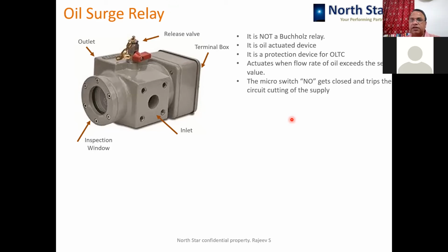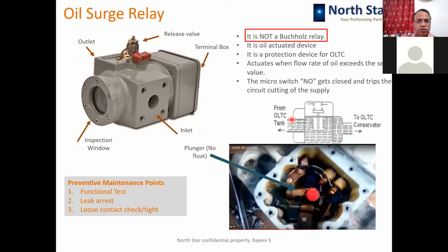So when the OSR operates, it is an indication that there is excessive arcing happening inside the OLTC. So you should look at the OLTC to see why that excessive arcing is happening. Maybe you have to take an immediate shutdown and do the necessary maintenance or replacement of the defective contacts, or you have to hold the OLTC operation and continue with the transformer working. So that is about the OSR. Okay. So again, like other devices, basic maintenance care can be taken of this device.